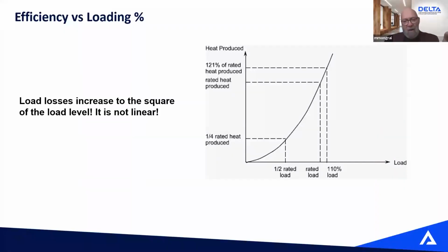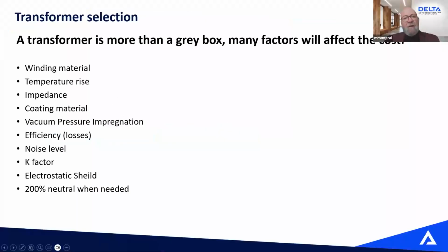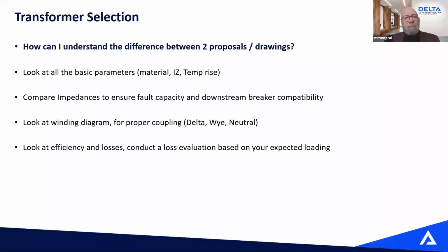So you take the transformer data sheet. If the full load loss is 1,000 watts, at 50% I'm going to generate 250 watts of loss. But the more you load, the more those losses will increase. So again, it's important to understand this when you select a transformer.